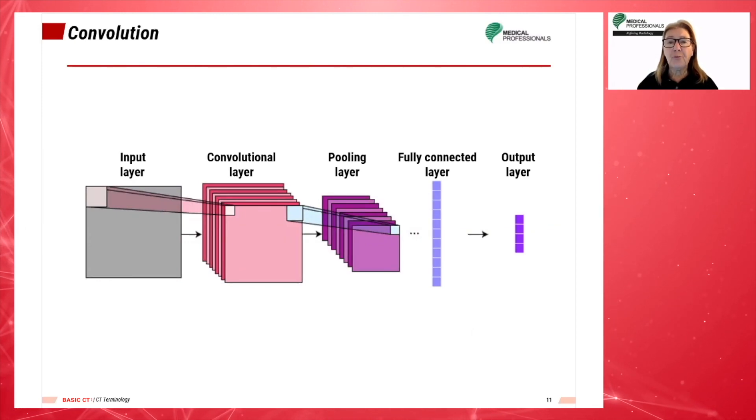Convolution, a general purpose algorithm, is applied to the reformatted data by the array processor. During convolution, the convolution kernel, which is a group of pixels, moves across the image, pixel by pixel, and is used to compute the value of the corresponding output pixel. Then, the back projection reconstruction algorithm reconstructs the image of the internal structures that are being scanned.